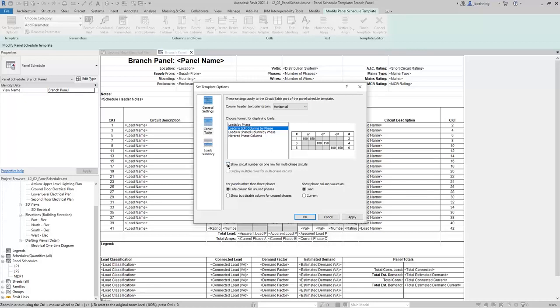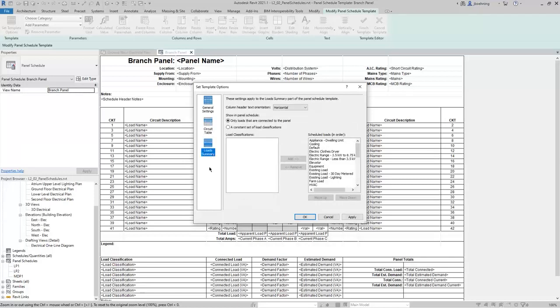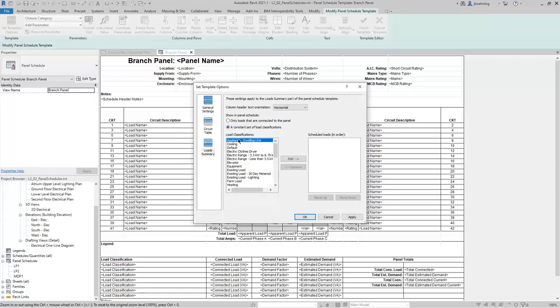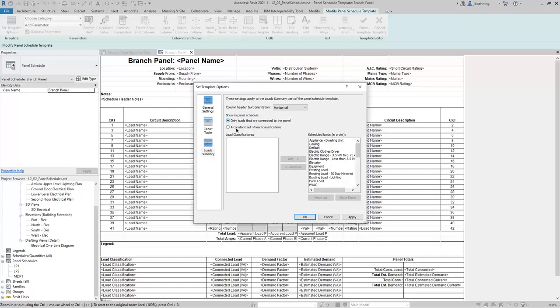You can choose whether or not to show the circuit number on one row for multi-phase circuits. For panels other than three-phase, you can choose to hide the column for unused phases, or to show but disable the column for unused phases. I'll leave it set to hide it. For show phase column values, you can choose either Load or Current — I'll leave it set to Load. In the Load Summary options, you can control the column header text orientation, and choose to show either only loads connected to a panel or a constant set of load classifications. I'll leave it set to only loads connected to a panel, and click OK.